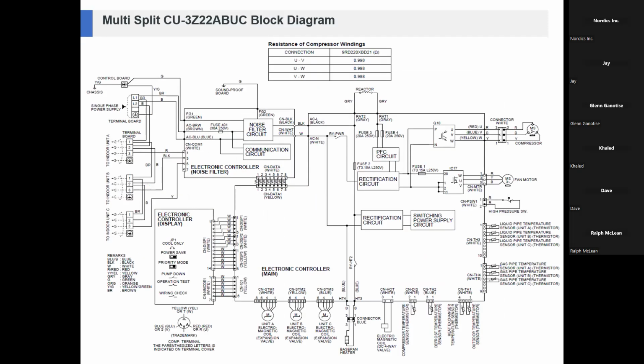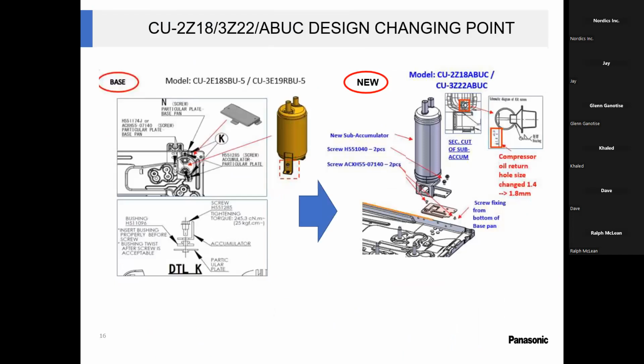That's your wiring diagram. And again, nothing different from the old one, except for an additional connection for your base pan heater. Okay, base pan heater. What the factory guys have improved is oil return. As you know, oil is super important for your compressor, to keep your compressor from burning out. You need oil constantly in your compressor for the windings. So between the old and the new receiver, they have increased the size of where the oil will return back to the compressor.